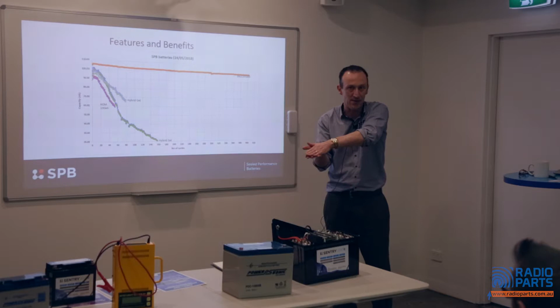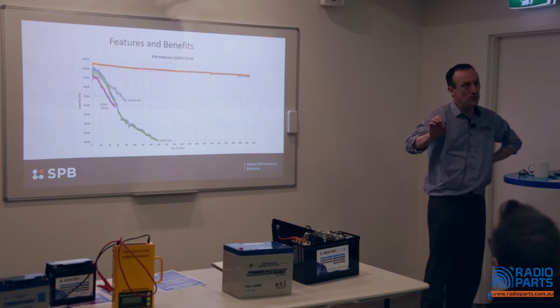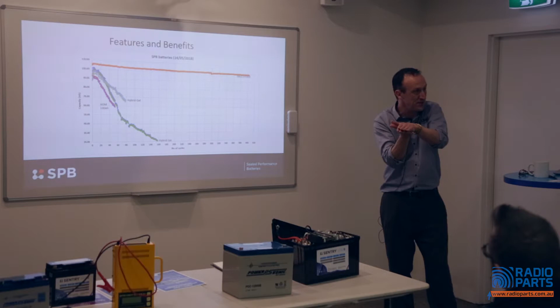So I can throw a 20 amp standard lead acid charger on that battery and the battery management system will take care of it. It's got the BMS built in to do it, but it won't do it as efficiently as with a lithium algorithm, in terms of the amount of current it'll deliver. Yes it will charge it, but it'll only bring it up to about 95% charge. It'll still bring it up, and won't have the issues experienced with lead acid like gel chargers versus AGM chargers - it just won't charge as efficiently and as fast using a lead acid charger.